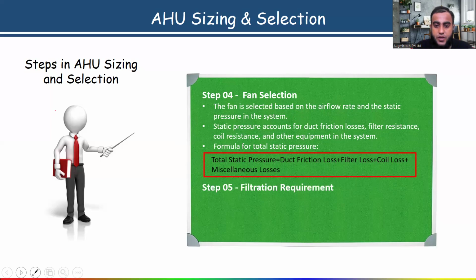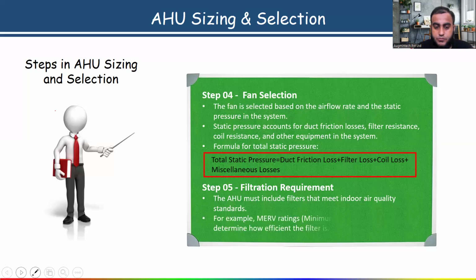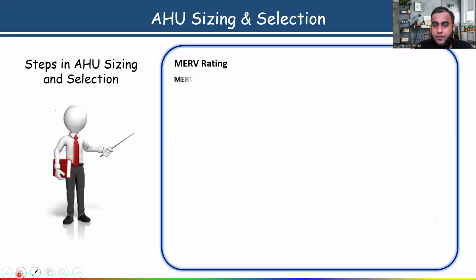Next step is filtration requirement. Different types of filters, as I told you. Remember, the AHU must include filters that meet indoor air quality standards. For example, MERV rating filters, minimum efficiency reporting value, determine how efficient the filter is. Here we have different types of filters. See, MERV 1 to 4 is the basic filtration. See, it shows what particle size it can capture.